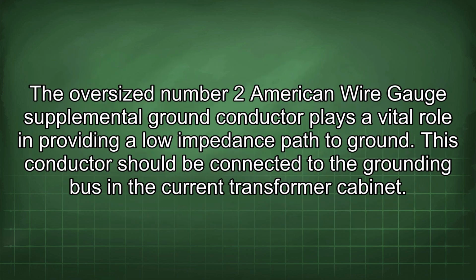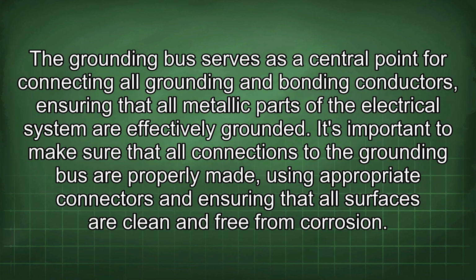The oversized number 2 American wire gauge supplemental ground conductor plays a vital role in providing a low impedance path to ground. This conductor should be connected to the grounding bus in the current transformer cabinet. The grounding bus serves as a central point for connecting all grounding and bonding conductors, ensuring that all metallic parts of the electrical system are effectively grounded. It's important to make sure that all connections to the grounding bus are properly made, using appropriate connectors and ensuring that all surfaces are clean and free from corrosion.